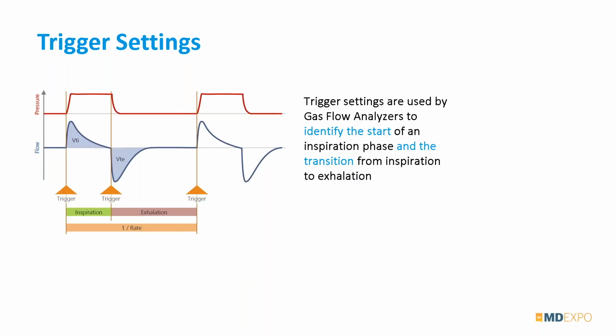But as you may know, with gas flow analyzers you don't only measure flow and volume, you also measure so-called breath-based parameters, right? So things like tidal volumes, peak inspiratory pressure, and stuff like that. To measure these, the gas flow analyzers analyze the measured waveforms of flow and pressure and then calculate these values based on timing parameters, okay? So these are typical waveforms you would see on your display when you have a ventilator connected to your gas flow analyzer. You see pressure rising during inspiration, for example, and going down to a base level during exhalation, and then the next cycle starts over here.